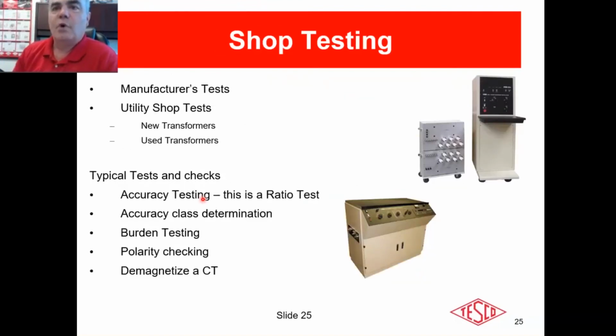Okay, so we talked about the manufacturer's test. Most utilities accept the manufacturer's test. Is there any risk to that? The only risk is that occasionally you'll see a mismarked CT, either with the wrong ratio or with the wrong polarity. You could check that yourself by doing a check after it's installed. Some utilities do that, and they do a ratio and check the polarity, make sure everything is good. We think it's a better practice to do it before, because you can also do the demag, but really it's up to you how you want to handle that.